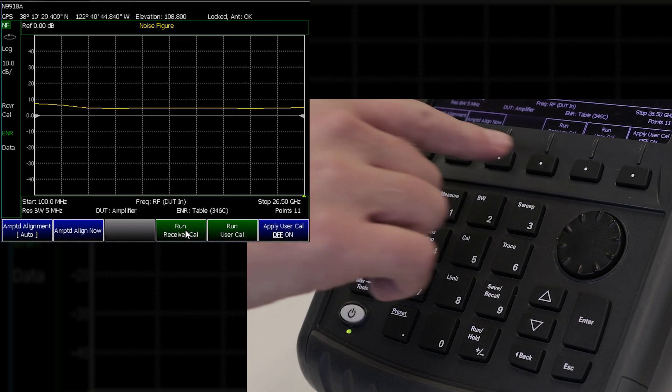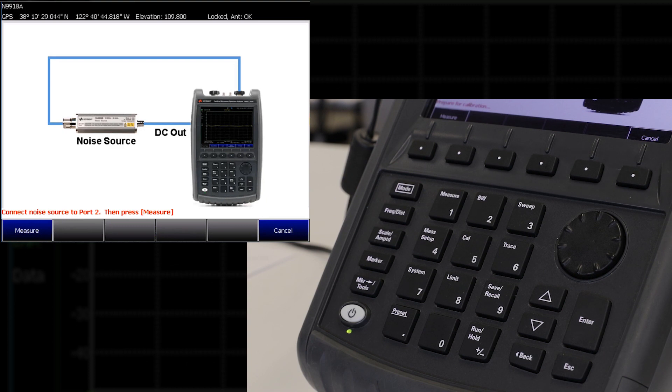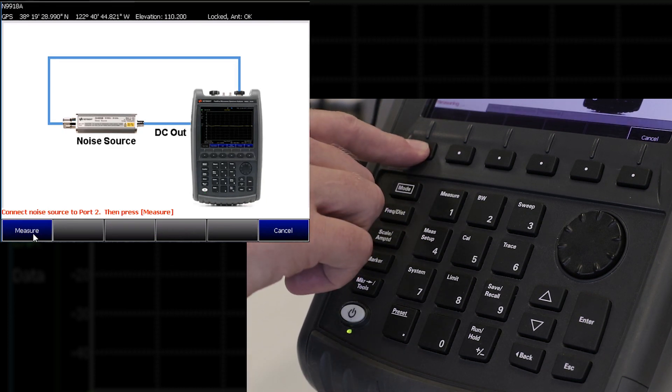FieldFox allows you to save and recall your ENR table for future use. Before I make my noise figure measurement, I need to run the receiver calibration. The receiver cal is used to characterize FieldFox at different receiver bandwidths — more specifically, it measures the gain bandwidth product at the different RBW values allowed in noise figure. The gain bandwidth is used in the noise figure and gain calculations, and it needs to be carried out before making any measurements. Under cal, receiver cal, notice the diagram that shows you how to connect the noise source to FieldFox, and then press measure.